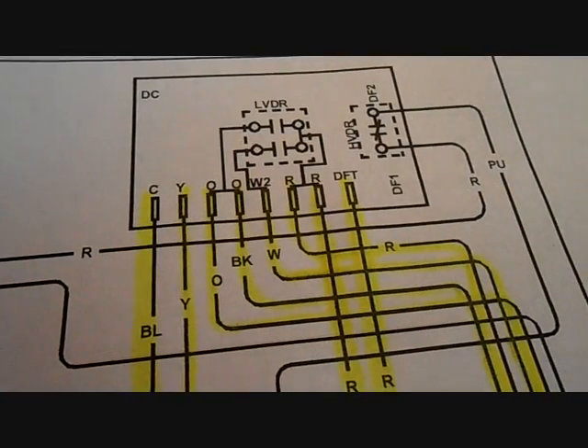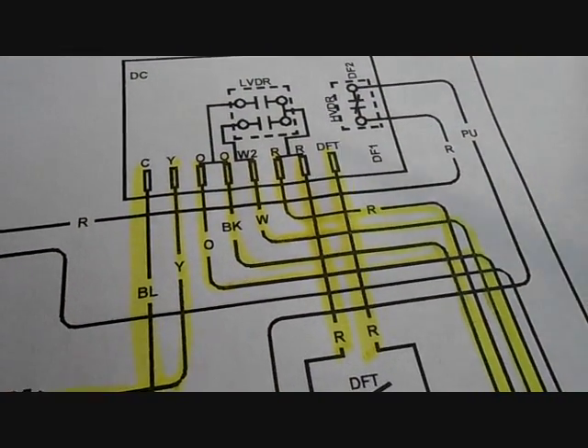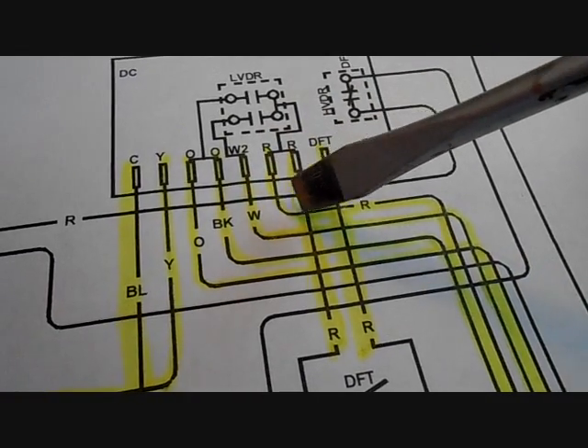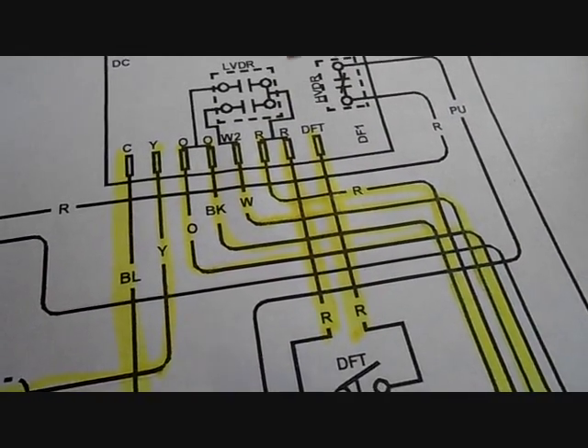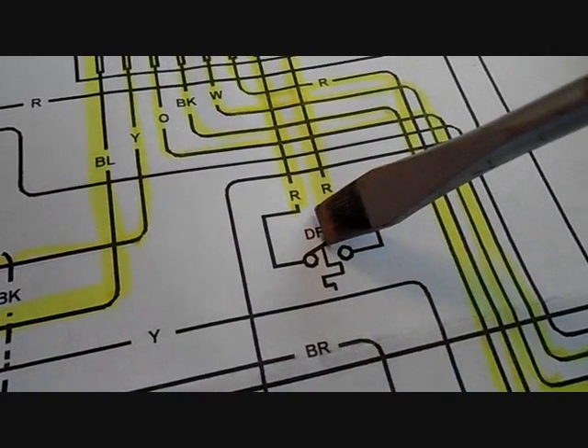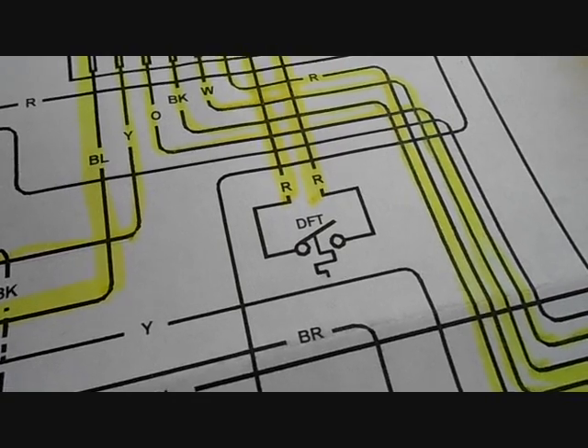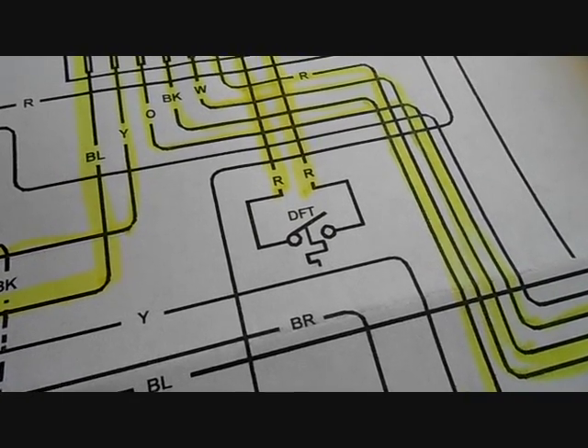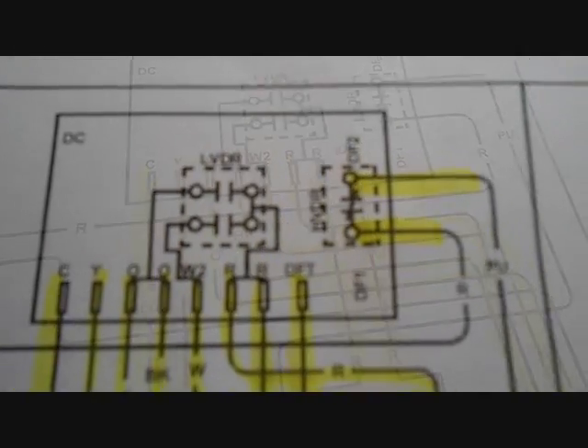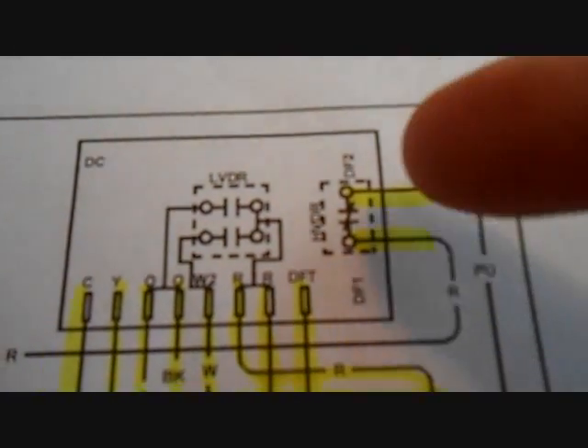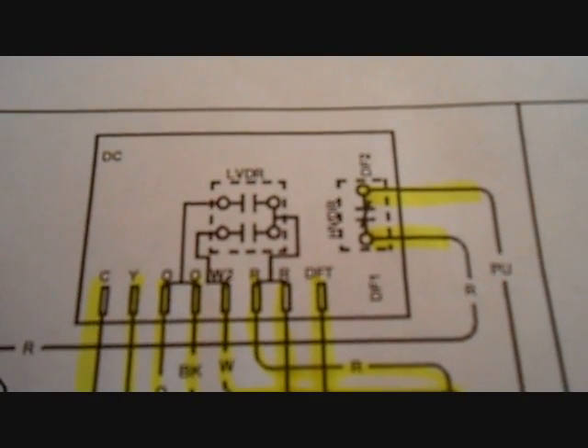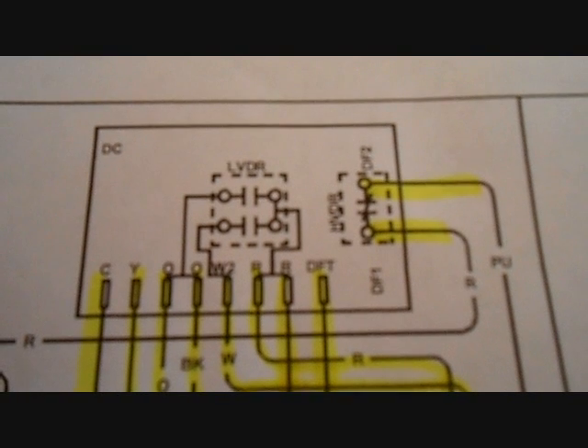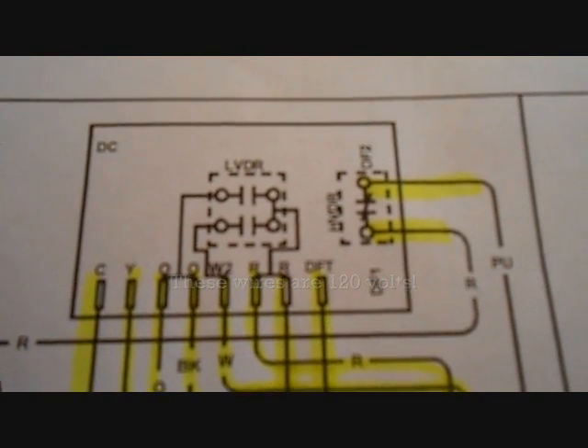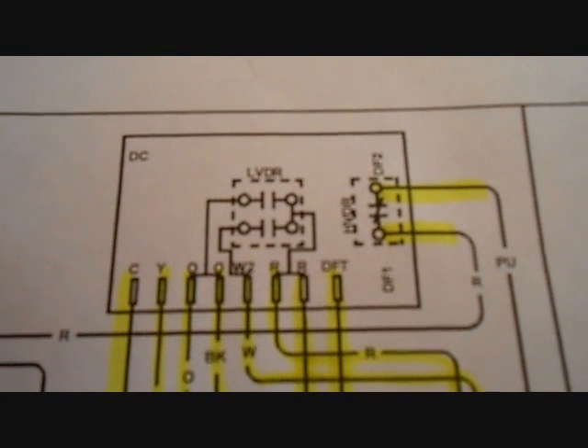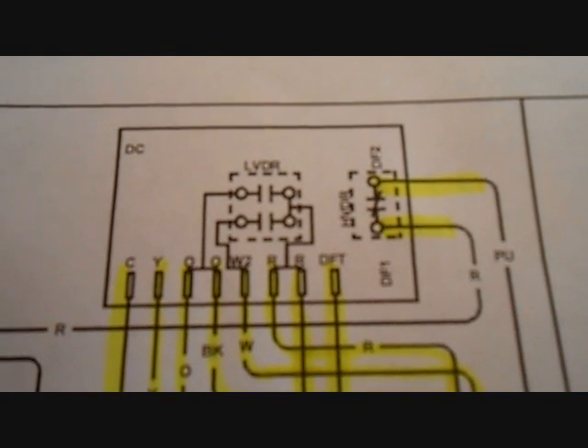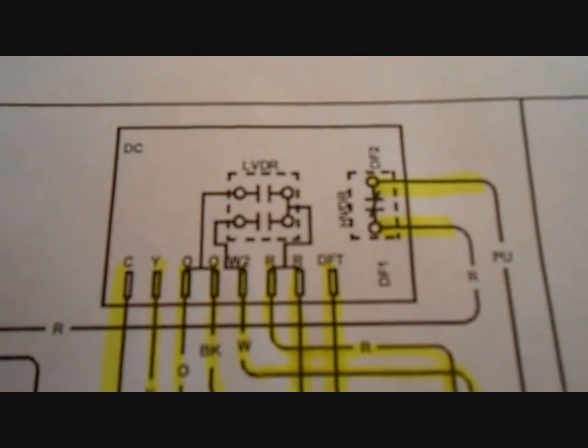The last three are all red wires. The first one coming from the low voltage field connection, or run down to that connection. The second one and third one go to the defrost thermostat. These little defrost thermostats are little clip-on thermostats that go on the outdoor coil that sense the temperature on the coil. The two wires on the side, on the right here, the purple and red, go to the fan relay. When defrost initiates, the contacts open and the fan shuts off. The reason why this happens, the fan shuts off to raise the head pressure. Higher head pressure equals higher heat. Melts the ice on the outdoor coil more effectively.